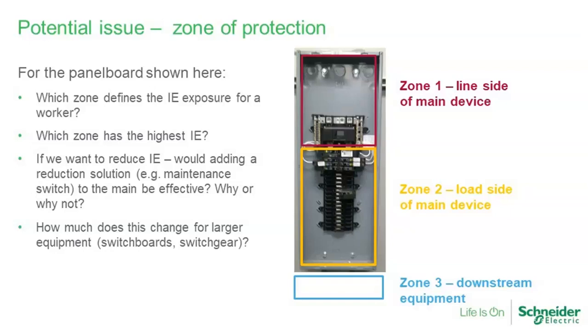But if I'm doing something in that panel, I want to test for voltage in that panel, I pull the cover off. Note that I'm exposed to both Zone 1 and Zone 2. I don't really have any kind of meaningful separation in there. There's nothing that isolates me from Zone 1 as soon as I pull that panel cover off. So I have to protect myself for whatever the worst case exposure is going to be. Simple enough with a low voltage panel board. What about other equipment? It's something we need to consider, and I'm not going to go through every potential scenario and tell you that for this you do this, for that you do that. But just think switchboards, low voltage switchboards. They're obviously bigger. They don't hang on the wall like a panel board.